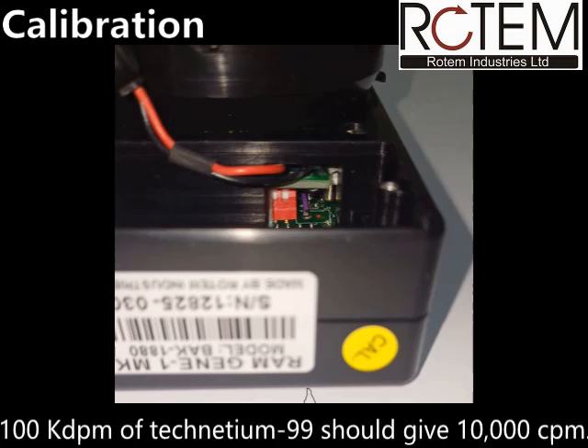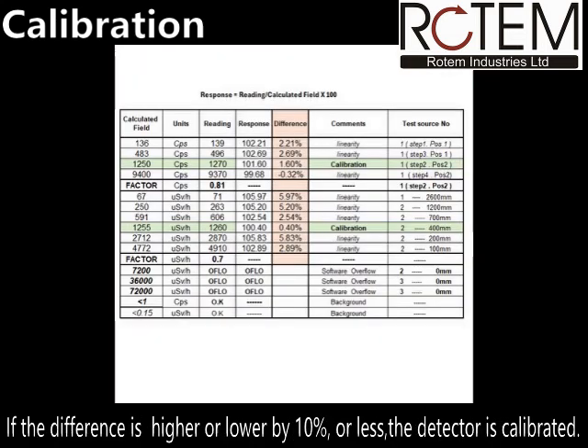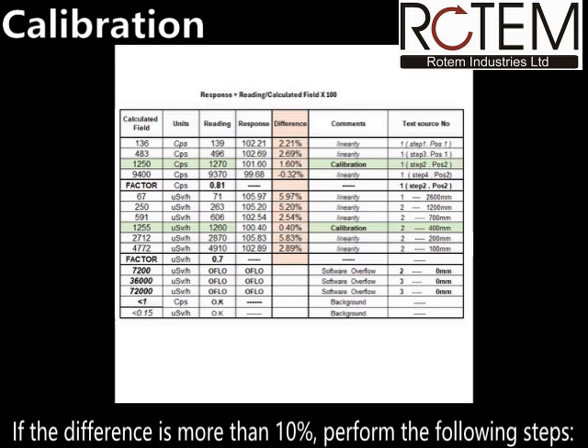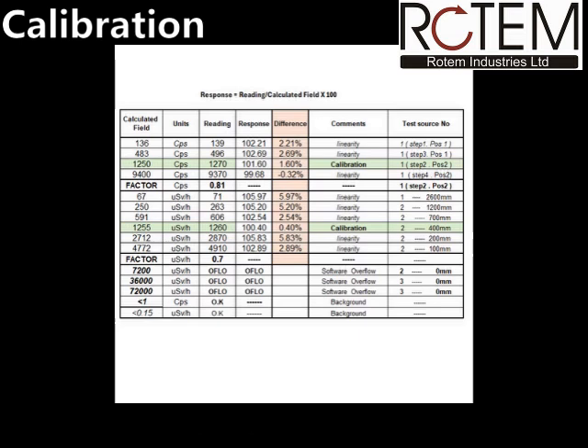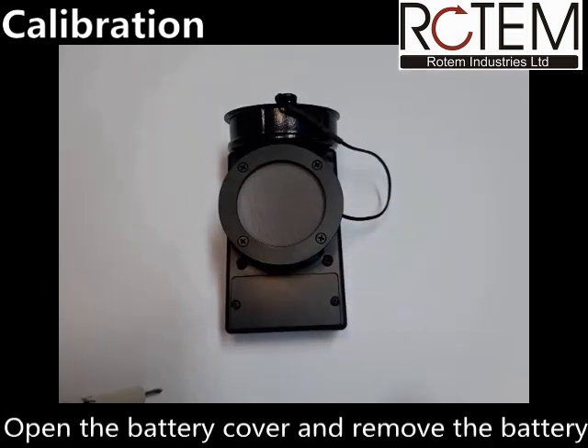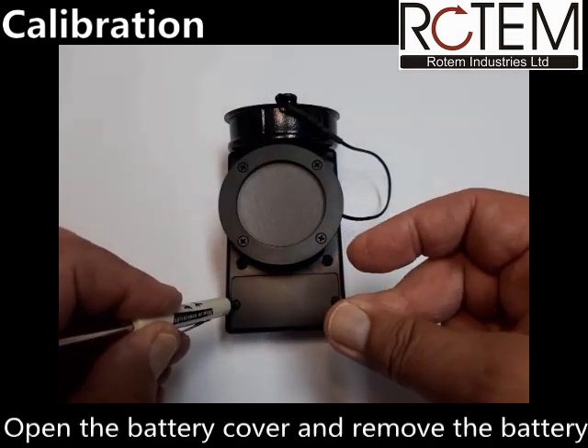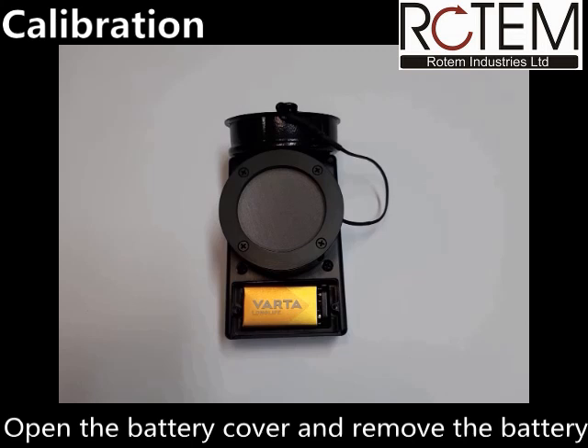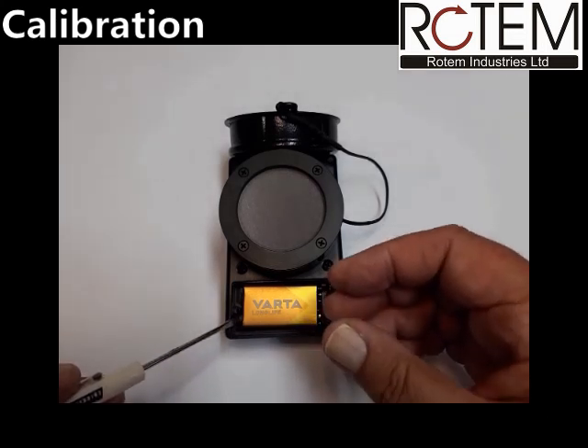For example, 100 kDpm of technetium-99 should give 10,000 CPM. If the difference is higher or lower by 10% or less, the detector is calibrated. If the difference is more than 10%, perform the following steps. Open the battery cover. Remove the battery.